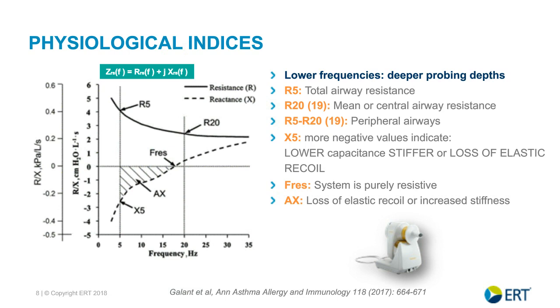Well, there's a point on the FOT tracing when pressure and flow are completely in phase. They're like a husband and wife walking down a park avenue on a sunny day, holding hands. They're perfectly synchronous. The pressure and flow are in phase and the system is at resonance. There is no reactance component. That's the resonant frequency, or FRES. The system has a pure resistance.